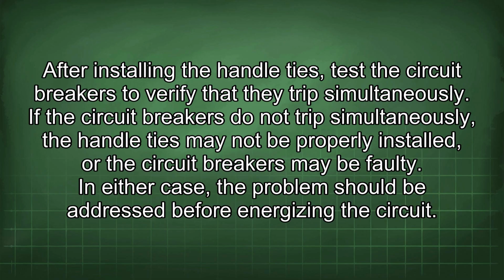After installing the handle ties, test the circuit breakers to verify that they trip simultaneously. If the circuit breakers do not trip simultaneously, the handle ties may not be properly installed, or the circuit breakers may be faulty. In either case, the problem should be addressed before energizing the circuit.